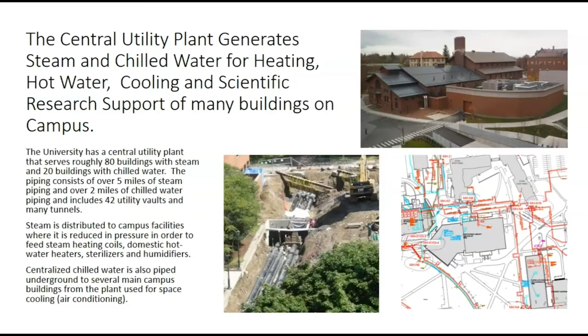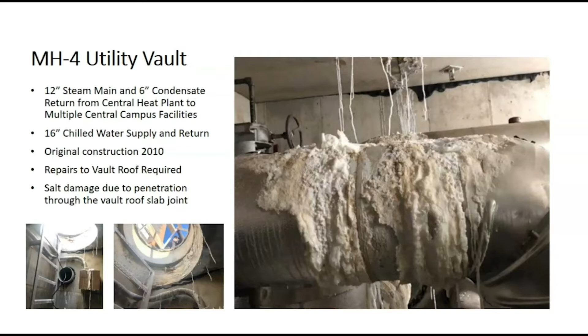Over the years, we've seen more significant salt penetration issues into our utility vaults. This is a photo of utility vault MH4, which supplies steam and chilled water to Central Campus. This has salt penetration through the roof seam as well as the manway, and has accumulation of salt anywhere from the steam jacketing to the carbon steel piping, the floor, and some of the electrical components inside the vault.